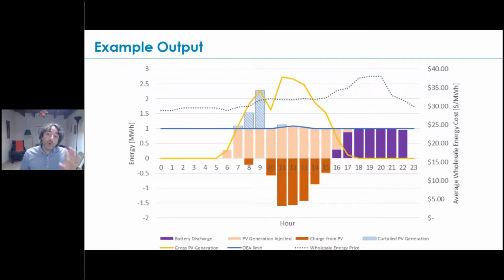This is the operation of a solar plus storage system dispatched to maximize revenues while abiding by the OEA. The yellow line shows the output from the PV system. The solid blue line is the maximum allowable export per the OEA. The pink bars show how much electricity from the PV system is exported to the grid each hour. The shaded blue shows how much electricity is curtailed given the capacity limits of the storage system. The red bars show how storage is charged from the PV system, and the purple shows how it's discharged. The dotted line indicates the wholesale market price—basically how much the developer is paid for any electricity exported to the grid.